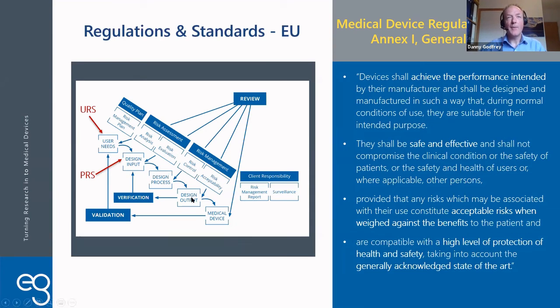You get a first product out, which you verify against the product requirements. And if it passes all of the product requirements, then you have a medical device that you can put into validation against the original user requirements. I'm not going to read through everything here, but you'll see the words about safe and effective, provided that any risks are acceptable when weighed against the benefits. That's this balance between safety and efficacy. Devices shall achieve the performance intended. This is making sure that you don't claim too much.